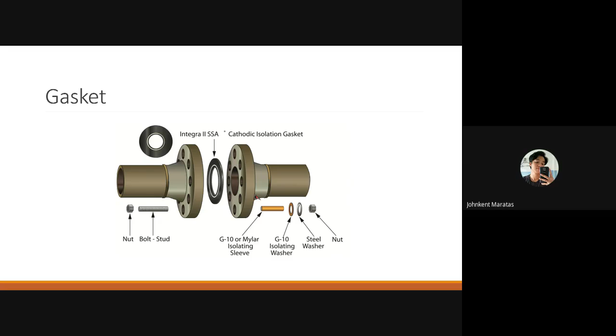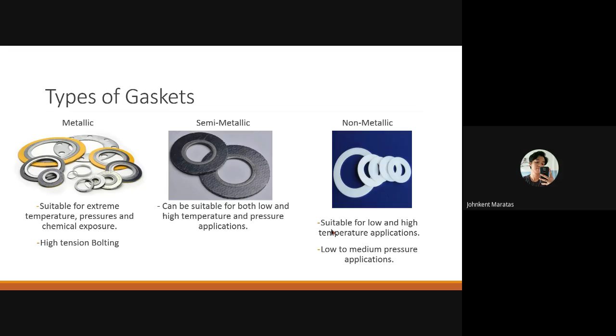And now there are three main types of gaskets. The metallic gaskets are suitable for extreme temperature, pressure, and chemical exposure, and high tension bolting. For the semi-metallic, they can be suitable for both low and high temperature and pressure applications. For the non-metallic, these types of gaskets are suitable for low and high temperature applications and low to medium pressure applications.